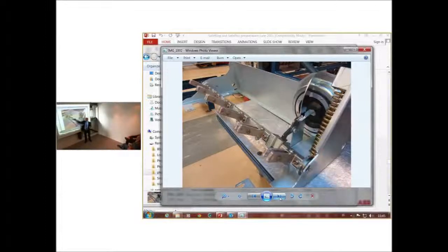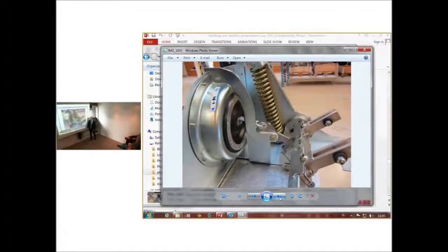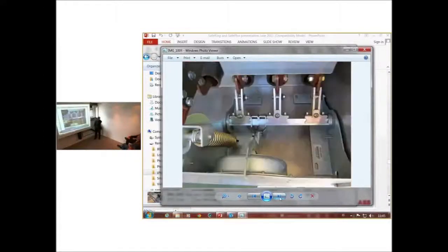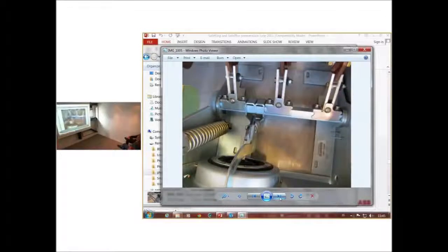This will earth both incoming modules. Click on this. Yeah. So you see, it will be charged. The pressure will act on this, and this spring will then short circuit the bushings. And here you see it's short circuit directly on the rear side of the bushing. And now I'll show you the video of this.